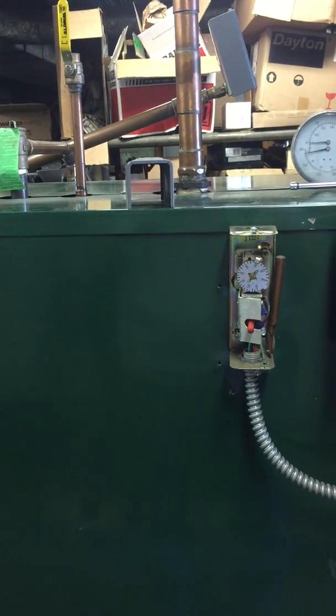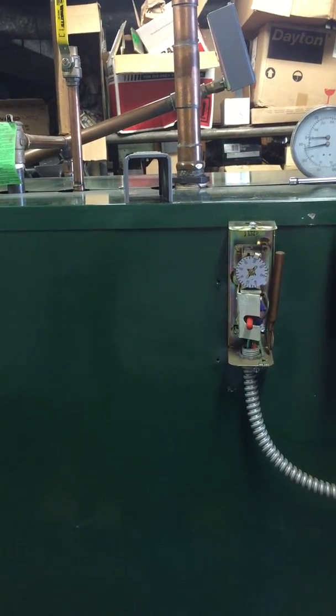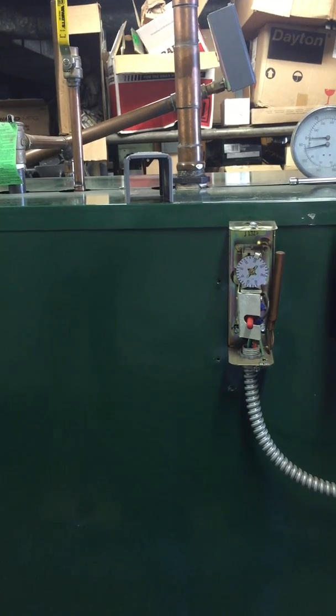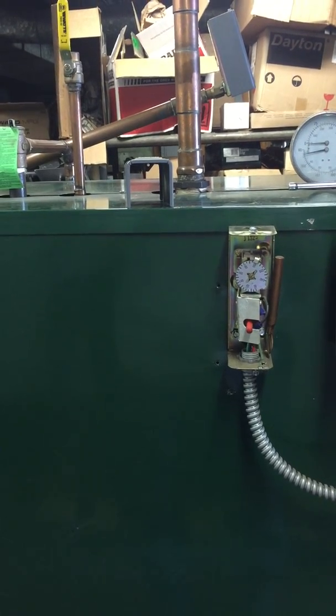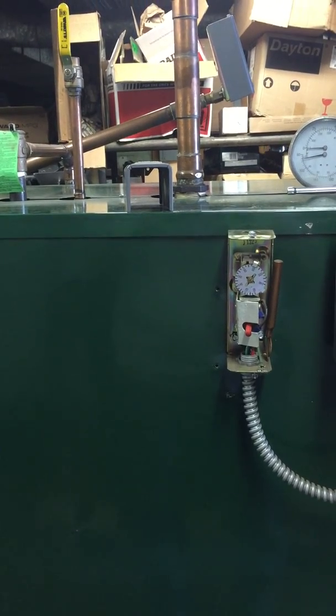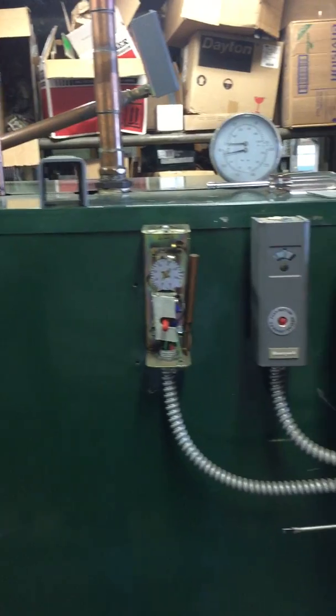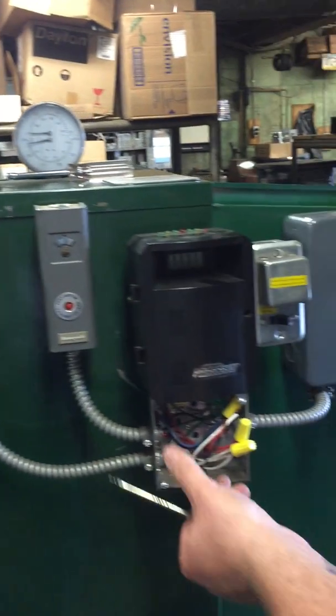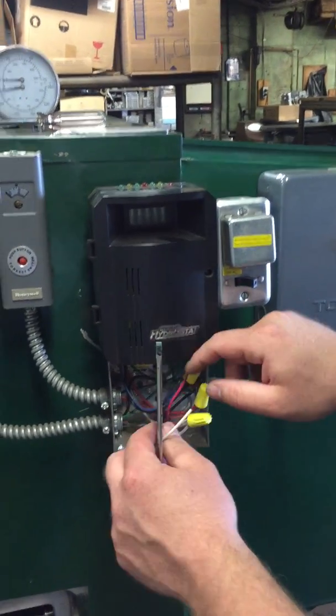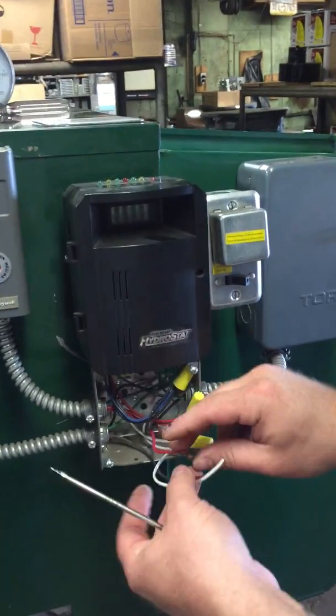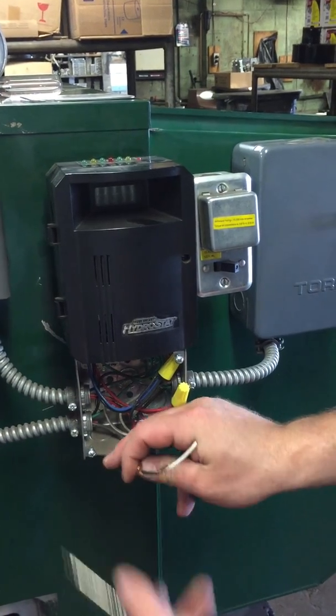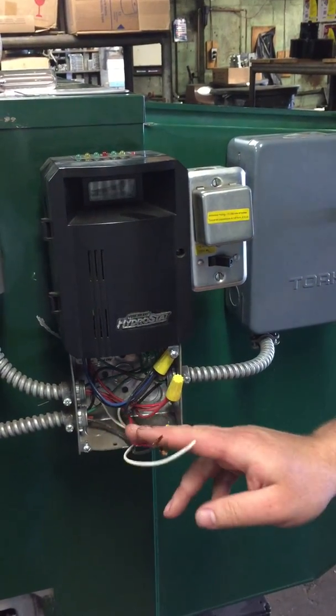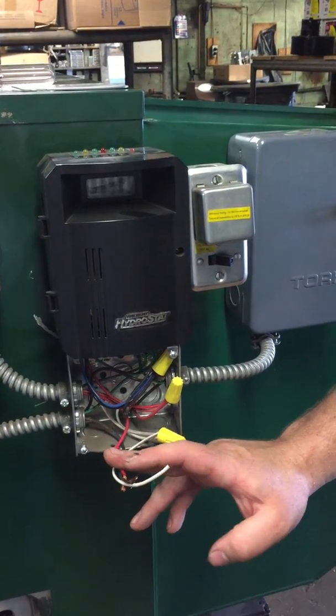You're going to run a wire from this 4x4 box down to the unit. You will use a 12-3 wire, which will have white, black, and red. You're going to see in here three hanging wires—your wires to wire into, your white, your black, and your red.